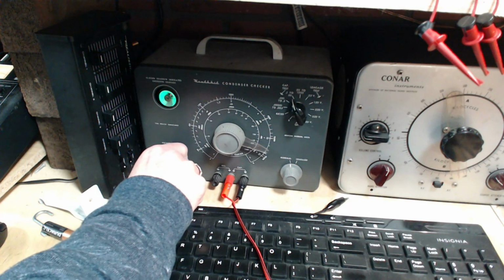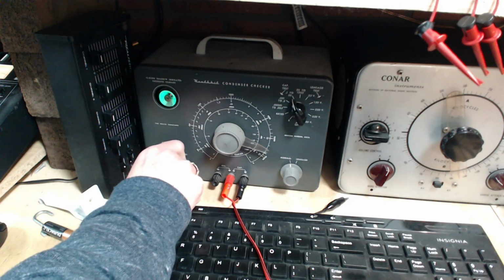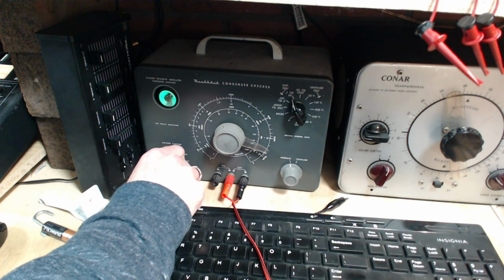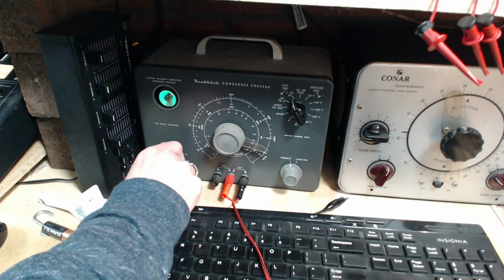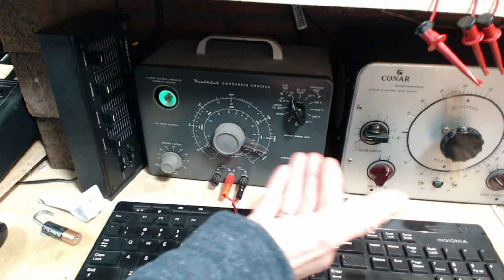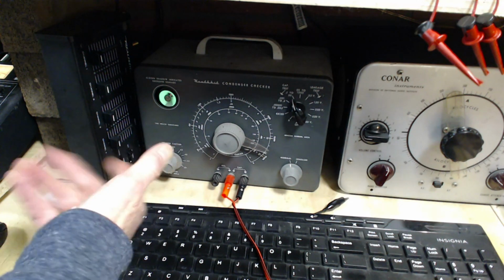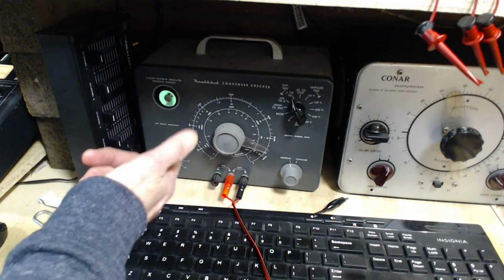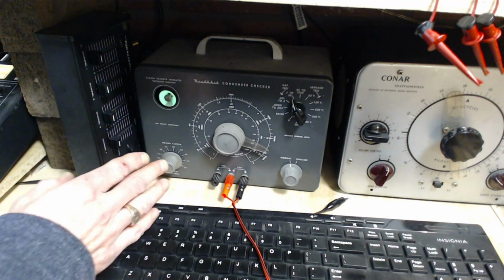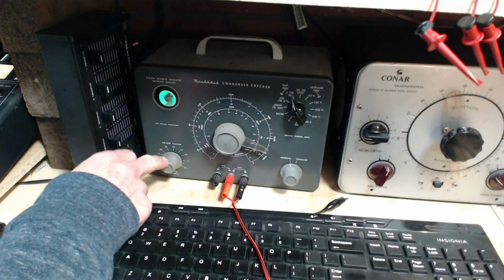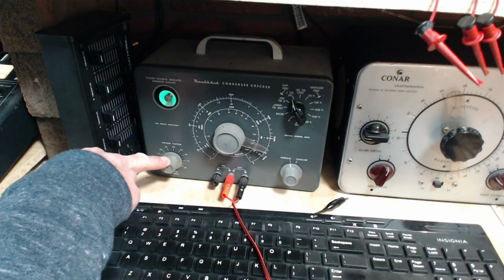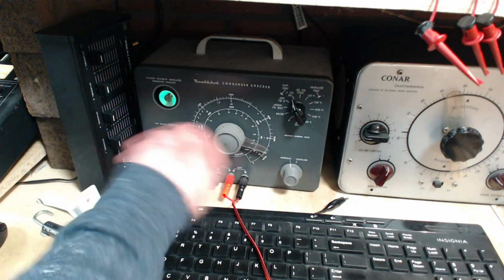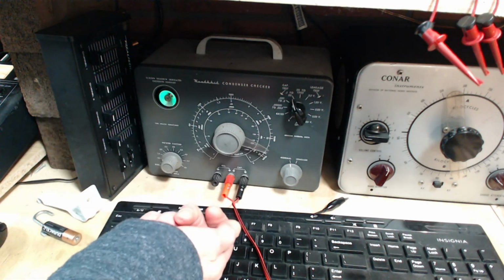So this is an adjustment where you are essentially, as I understand it, balancing the leakage resistance in the capacitor against something in the bridge circuit. And the result of doing this is you'll find out what the power factor is on your capacitor. And lower is better, higher is worse.